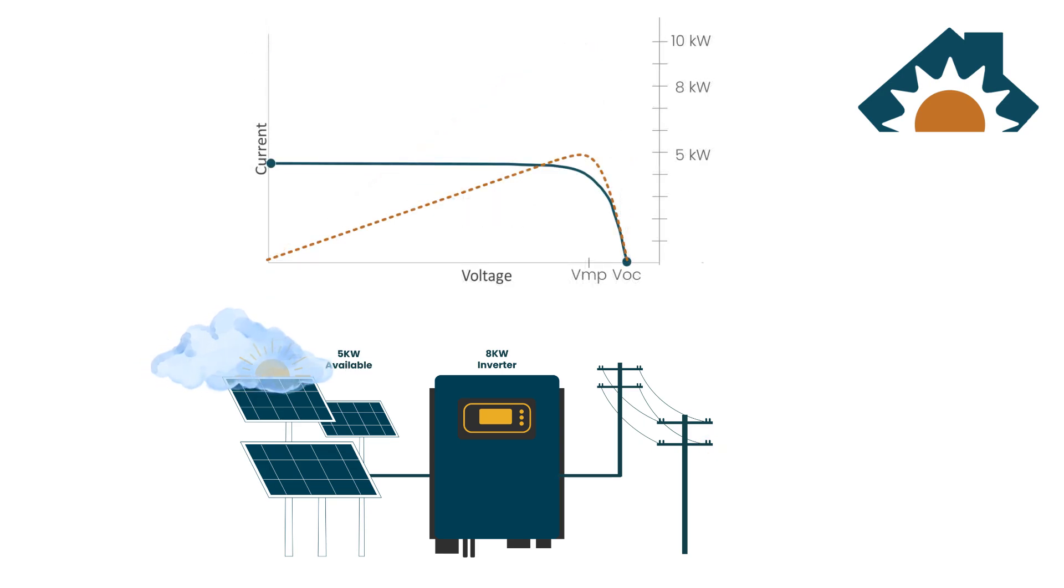Now, although you may have a 10 kilowatt array on its best day, that power won't always be there, for example, on a cloudy day. In this case, let's say you only have 5 kilowatts available at the array and you haven't derated the inverter. Then the inverter will try to track to the maximum power point in order to maximize production to get as close to 8 kilowatts as possible. And that's a quick explanation on how inverters can have more power connected to it than its output rating.